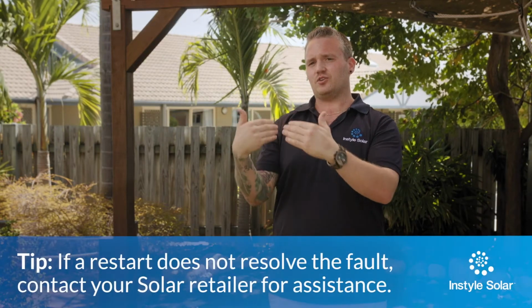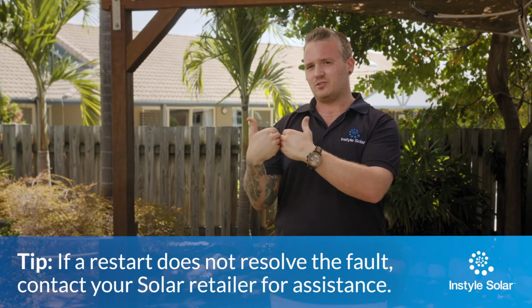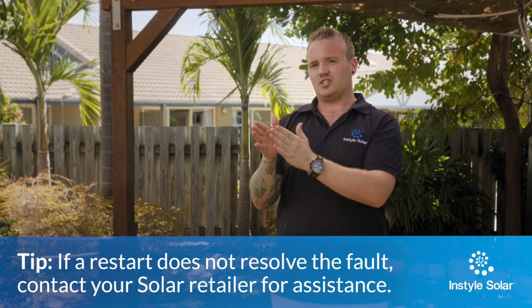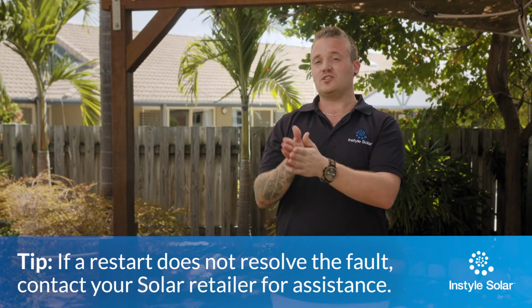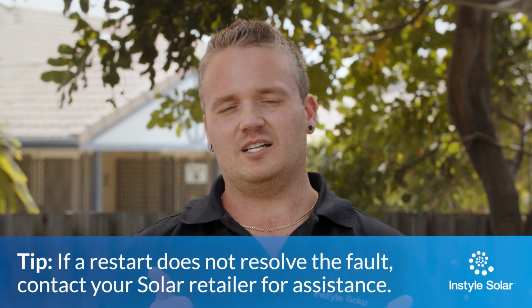Some faults are as simple as a voltage clip. Okay, so this means maybe your system is producing so much power, at the same time other people in your neighborhood were producing so much power, and everybody was exporting too much into the grid. Now, the grid network wasn't actually designed for this, so what's going to happen is you're going to have voltage pushback. This is called voltage rise. When this happens, your inverter may get too much voltage sent back to it from the grid, and as a safety precaution, it's going to shut itself down. So this is where you need to do a simple restart when you have a voltage clip, and your system should be ready to go. Now, this is just a safety precaution built into the inverters.